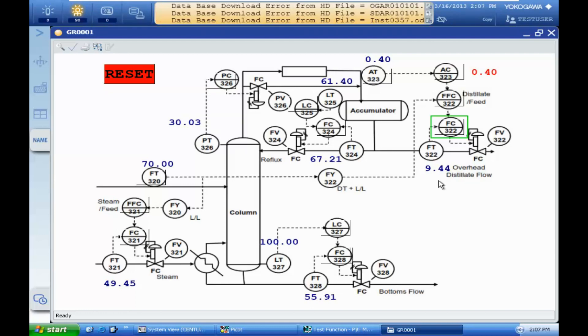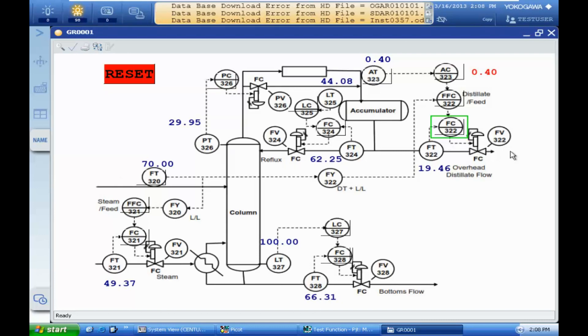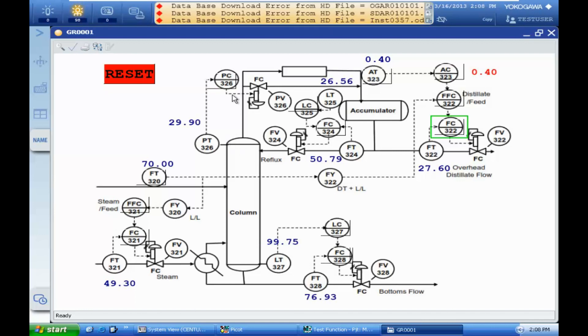This example is not a 100% perfect distillation tower. In a real application, we should have safety measures like SDVs here, we need the SDV at the outlet, and some PCVs here — if pressure is increased, something should be done. Or a PSV that is connected to the flare mechanism.